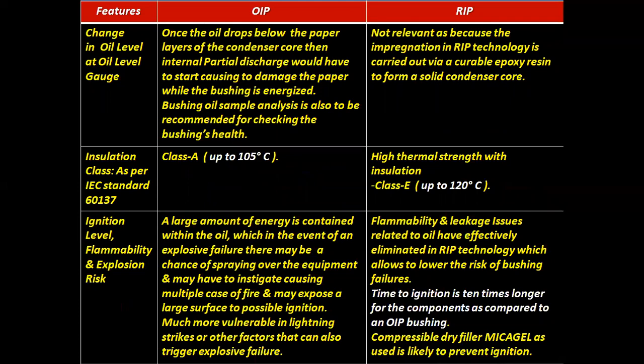Change in oil level at the oil level gauge. Once the oil drops below the paper layers of the condenser core, internal partial discharge will start, causing damage to the paper while the bushing is energized. Bushing oil sample analysis is also recommended for checking the bushing's health. It is not relevant in the case of RIP bushings because the impregnation in RIP technology is carried out via a curable epoxy resin to form a solid condenser core.